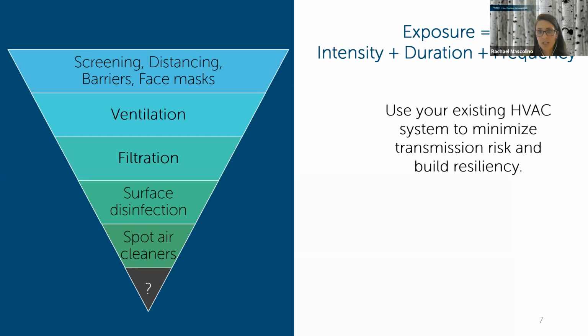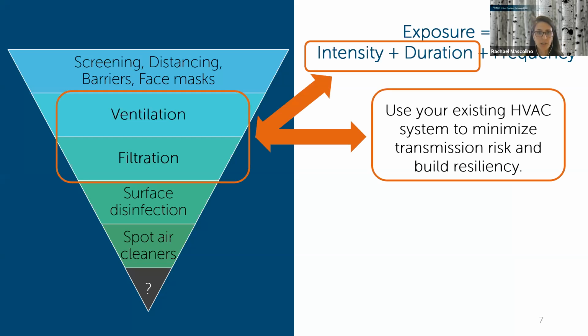So here is that hierarchy. This is based on minimizing exposure to any contaminants, whether it's this virus or a flu or a cold that we would typically see in buildings in Vermont in the winter. So intensity and duration can be addressed with ventilation and filtration, and that's why we see these right at the top. That formula of exposure equals intensity plus duration plus frequency.